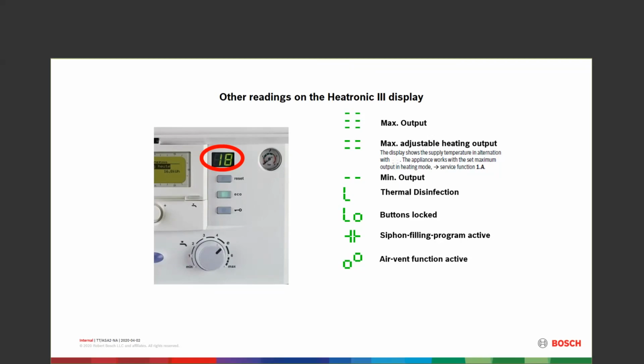Next one is the air vent function. Anytime we turn the control on brand new, reset the control back to factory default, or actually go into service functions, we can turn on this air vent function. What it does is it turns the pump on, the pump pulses, comes on, off, on, off.